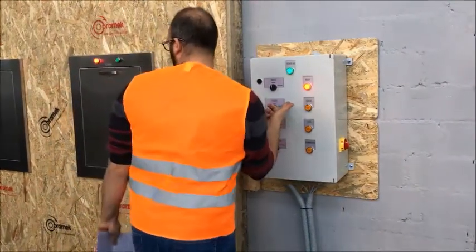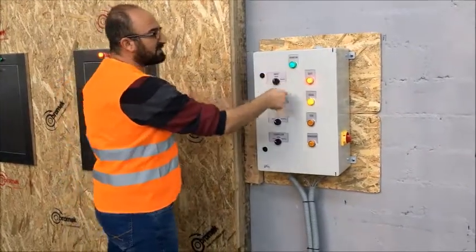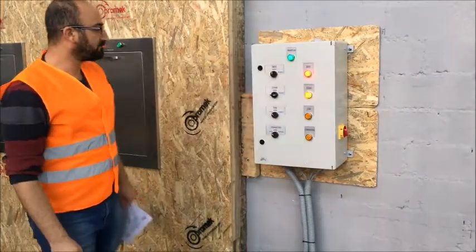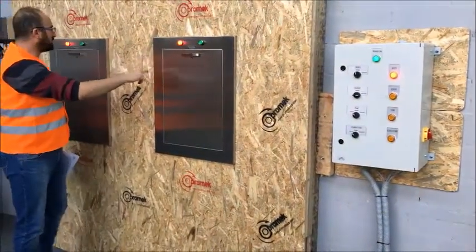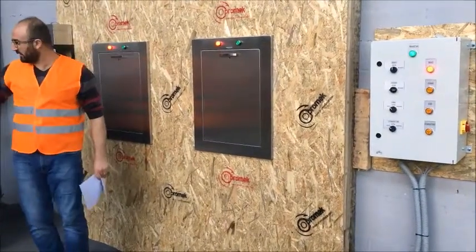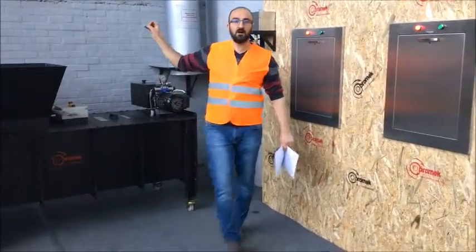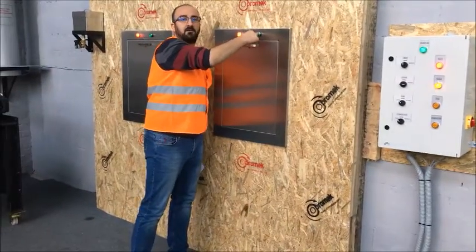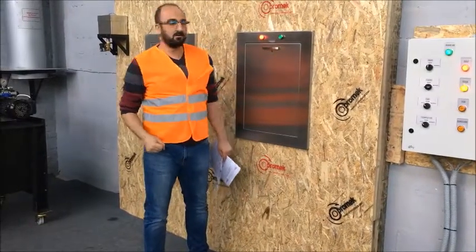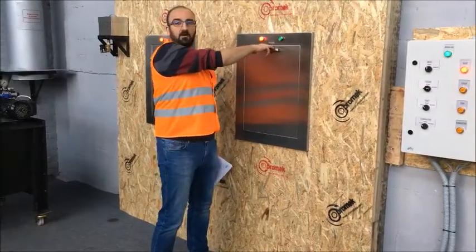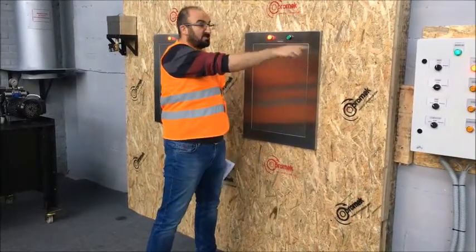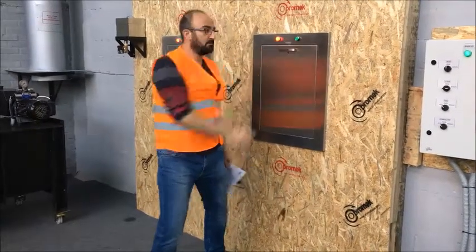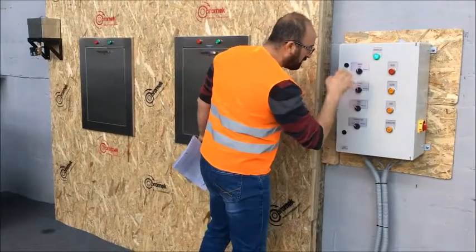When the cleaning is active, the system turns into the busy signal. And all the doors, as you can see, and additionally the compactor and the fan are in the disabled position. When you press the button, you see nothing. Nothing happens in the door. When you try to pull it back, since the cleaning is active, you cannot take this door out.